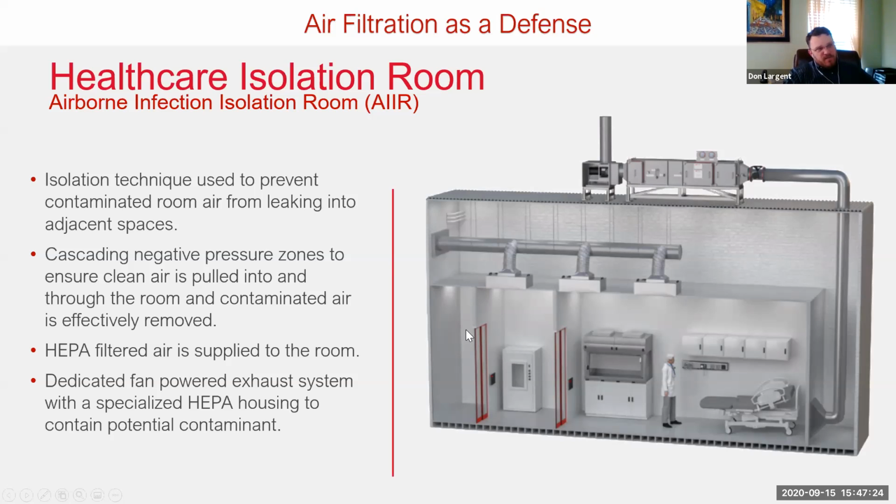But what we have here is basically the hallway, the ante room, and then the patient room, all supplied. Well, the ante room and the patient room are supplied with HEPA air, but you have a negative pressure cascade, which forces, when these doors are open, the air to move from the hallway into the ante room, from the ante room into the patient room. And that way it comes across the patient and will remove any contaminant out of that space without exposing it to the healthcare or minimizing any potential exposure to the healthcare professionals and anyone else in the facility.